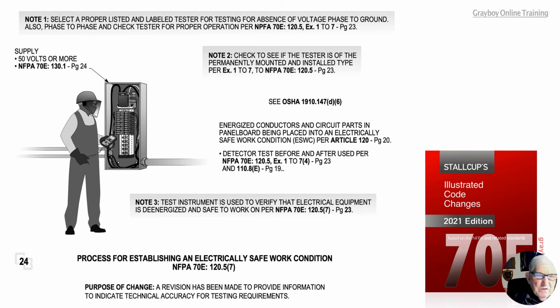Now, this illustration deals with the process for establishing an electrically safe work condition. And of course, we know that 120.5 lists this information, but notice there's been an item 7 that has been added. The purpose of change was a revision, and the revision was made to provide information to indicate technical accuracy for testing requirements.